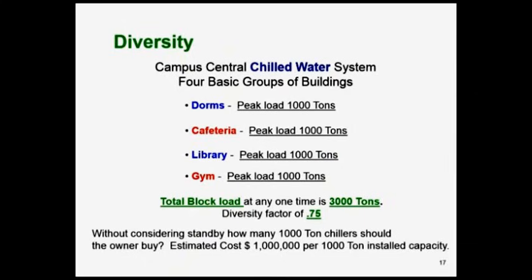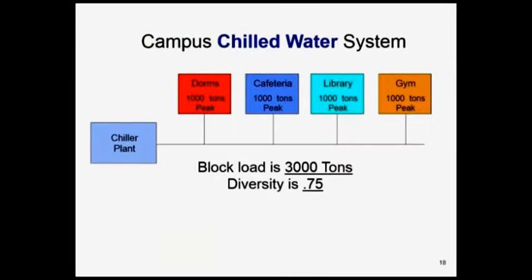What that means is the kids can only be in one place at a time. So where are the kids? Each individual building might need 1,000 tons of cooling, but if I look at the whole campus at one time, all I need is 3,000 tons. So how many chillers are you going to put in? You're going to put in three 1,000-ton chillers for 3,000 tons total, or 4 1,000-ton chillers for 4,000 tons total, and we're not going to play the old game of standby.